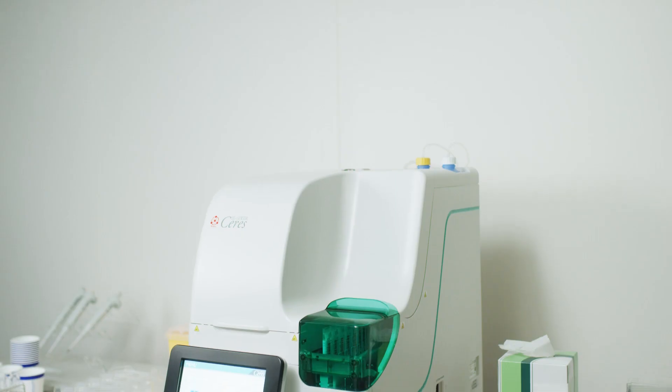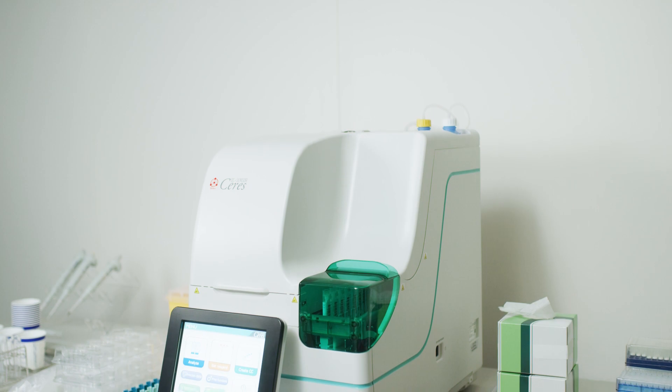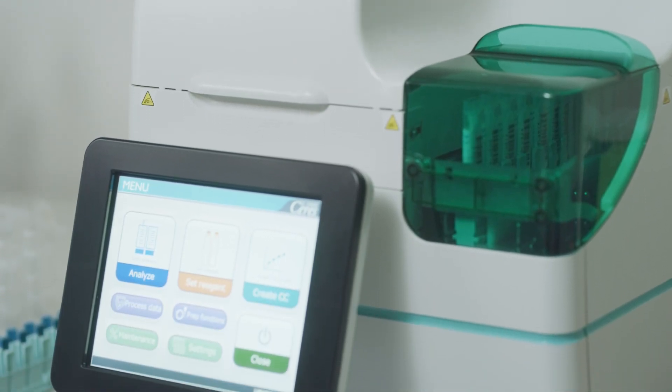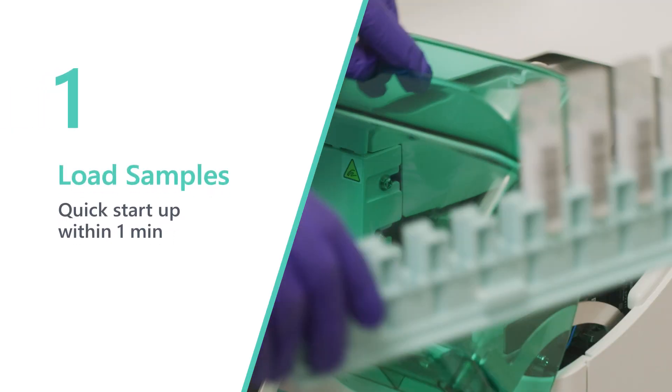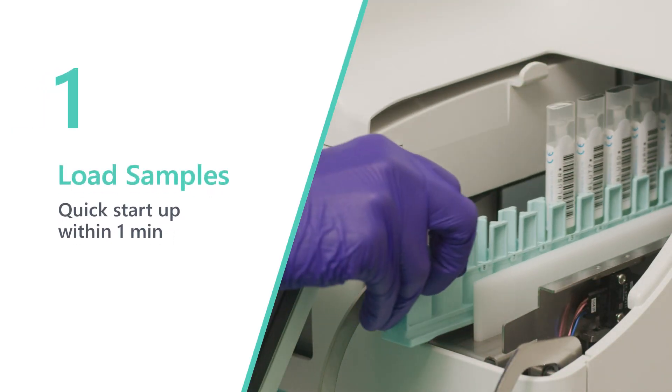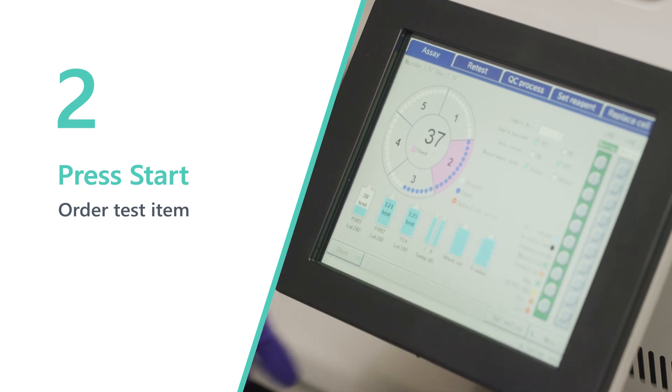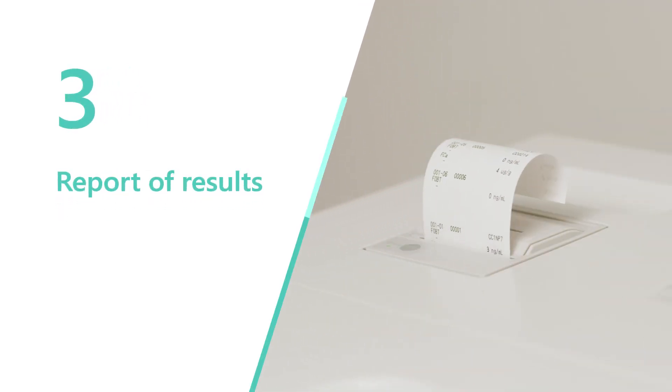OC Sensor Ceres is now even more user-friendly. The analysis is completed in three simplified steps. OC Sensor Ceres starts up quickly within one minute. Set the sampling bottles on the sample rack and load it onto OC Sensor Ceres. Select test items on the screen and press the start button. The first test results are reported in 8 minutes for FIT, 10 minutes for fecal calprotectin, and 11 minutes for both items analyzed from a single sampling bottle.